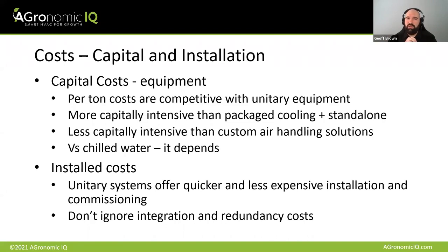Don't ignore redundancy, in particular looking at things like chilled water. If you're doing a big central plant system, by definition it's a centralized system that feeds your whole facility. If that central system goes down, you have a major, major problem on your hands. So how do you build in that redundancy in something like a central plant or any other equipment type for that matter? So always something to be aware of.